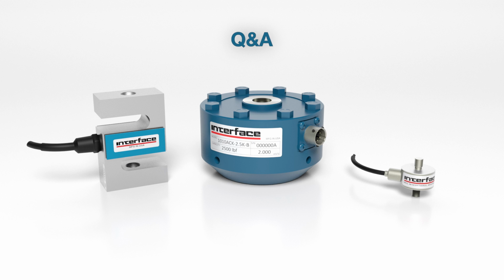The shunt cal data is useful down the road if you want to do a sanity check or verification, if you will, on the calibration on your system. Some customers do use that as a form of calibration. The con to it would be that you're limited somewhat to the accuracy of that resistor that was used. We typically perform simulated calibrations here or actual in-rig force calibrations for our instruments and indicators here. But shunt cal can be used.